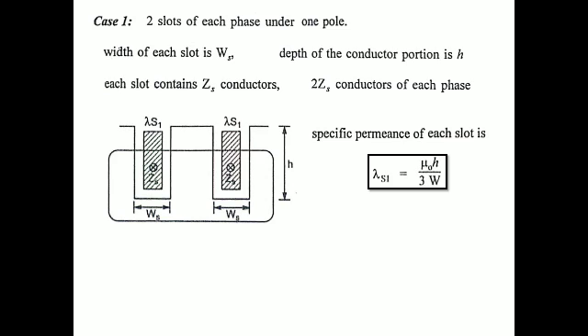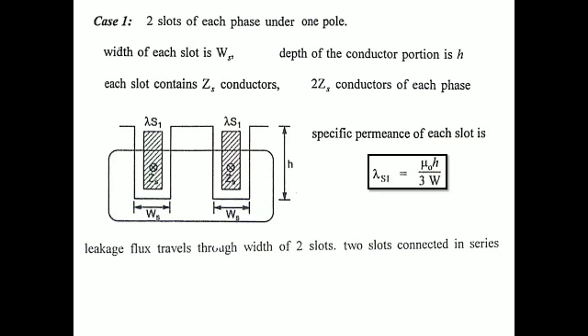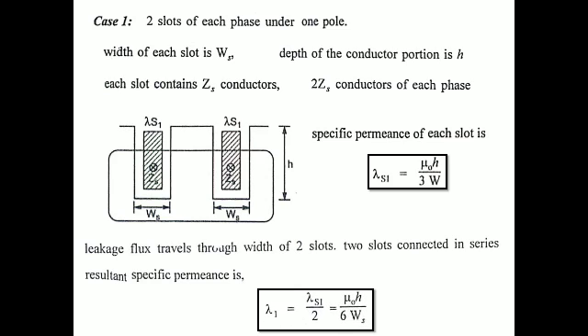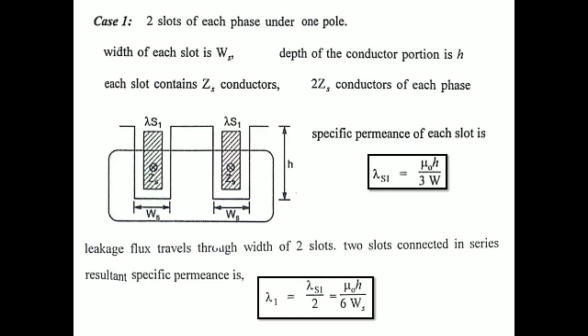The leakage flux of the two slots is connected in series, so for the resultant specific permeance we divide by 2. The value becomes: λ₁ = λ_s1 / 2 = μ₀·H / (6·Ws). This is the specific permeance value for a phase having two slots, considered as lambda_1.